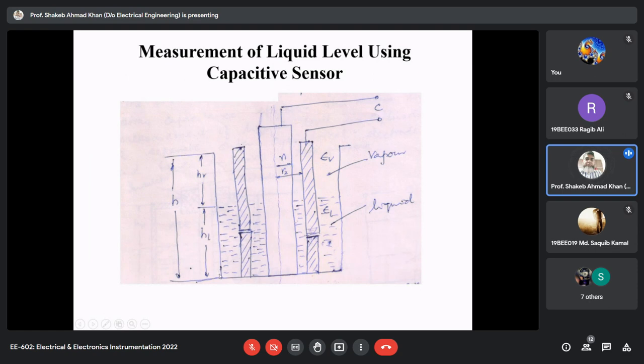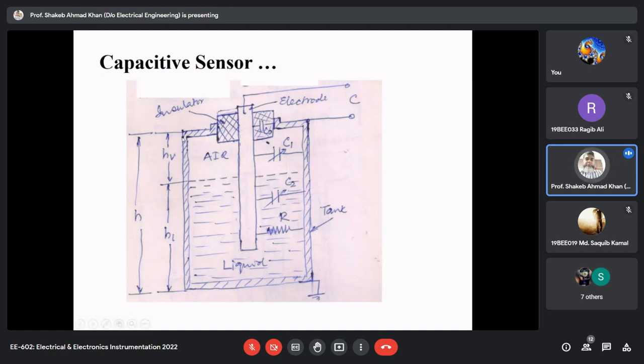Now we can improve upon this: if the tank is metallic, then this tank may work as the outer cylinder of the capacitive sensor, and we require only one thin electrode. Here your tank is made up of metallic material and it is grounded also. So this will work as the outer electrode, and we require a thin solid electrode. A capacitance will form between this inner electrode and the tank working as the outer electrode.